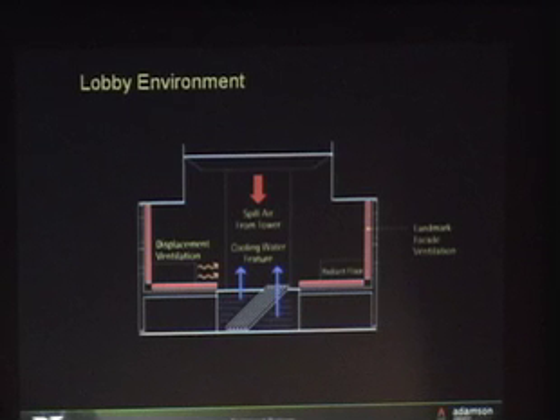We keep it just slightly above the dew point. So what it does, it actually provides a convective and radiative cooling effect to the space. But even more important, you don't add moisture to the room. So by not adding moisture to the room, you save on the AC load, which saves on energy. You save on water that we would have to replace here for makeup, and the water that comes out of the cooling tower, because if you're evaporating, that energy ends up coming out of the cooling tower. So overall, it's not just a visual feature to the space, as most people would see. It's actually an integral part of the conditioning system.